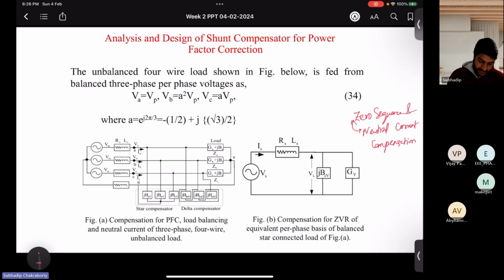So star, I am telling, neutral current and power factor compensation. So once you put in the star compensator, the neutral current will go to 0, and effectively the source will think that some resistive loads are connected to it. However, it is still not balanced. The load is appearing resistive to the source, but not balanced.